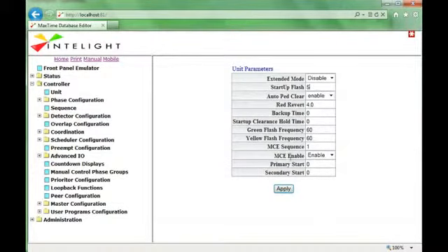When you power up the controller, it's in cabinet flash until the controller becomes alive. It goes through a diagnostic period, usually about 8 seconds. So you get 8 seconds of cabinet flash, and then this interval comes in. Now, if you have a 0 in this parameter, it just gets skipped and goes to the next interval. However, you can put time in here.